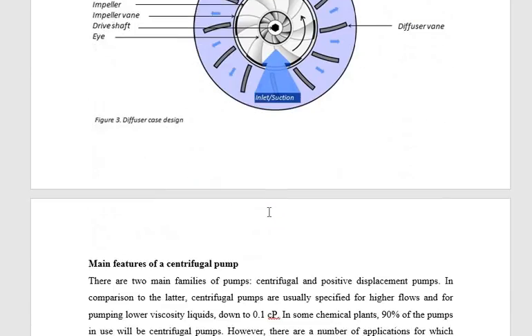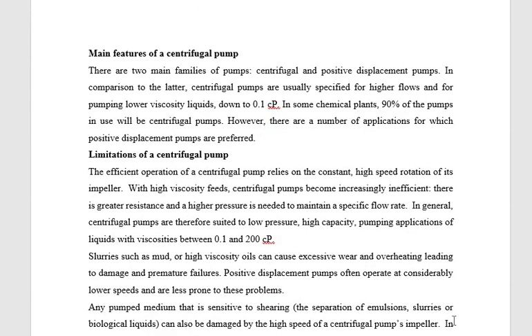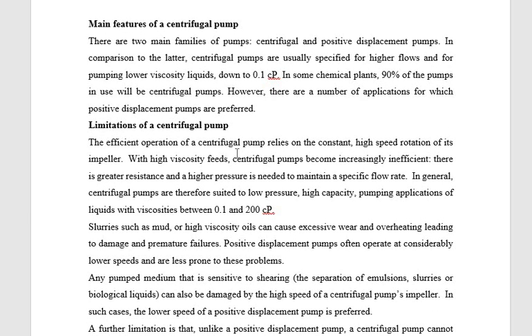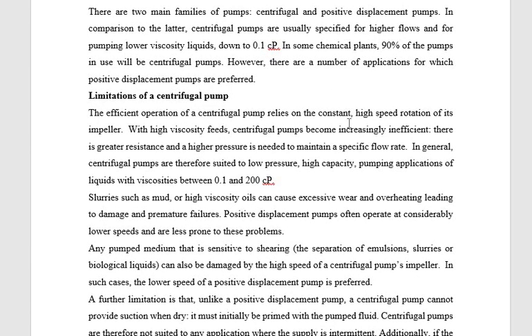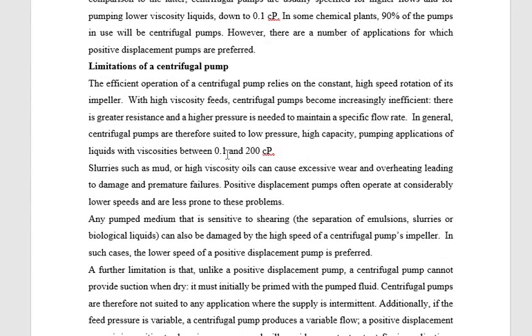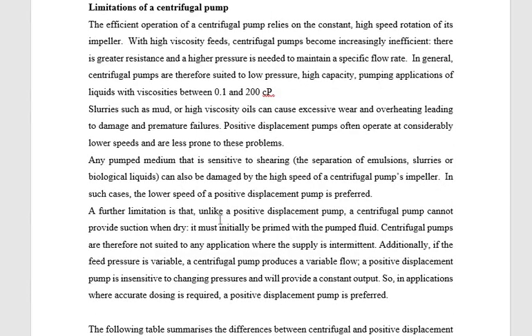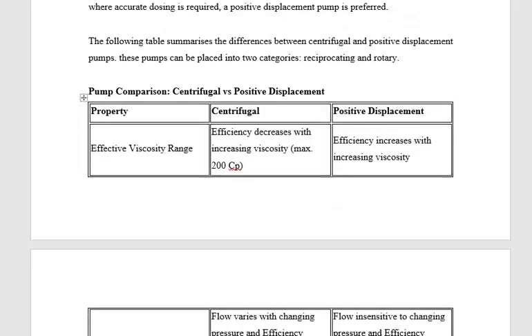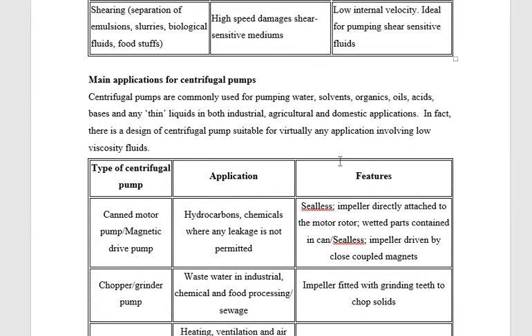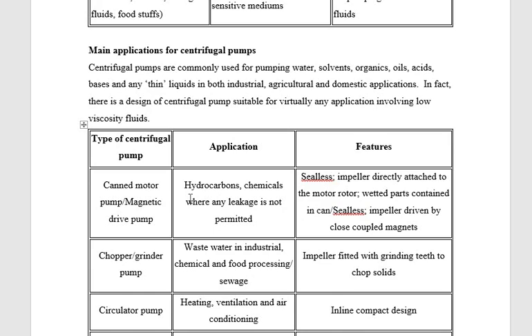There are two kinds of pumps: centrifugal and positive displacement. Our focus here is the centrifugal pump. There are some limitations: efficient operation relies on constant high-speed rotation of the impeller; with high-viscosity fluids, centrifugal pumps become increasingly inefficient, and there is greater resistance and a higher pressure is needed to maintain a specific flow rate. Applications of the centrifugal pump are also discussed.